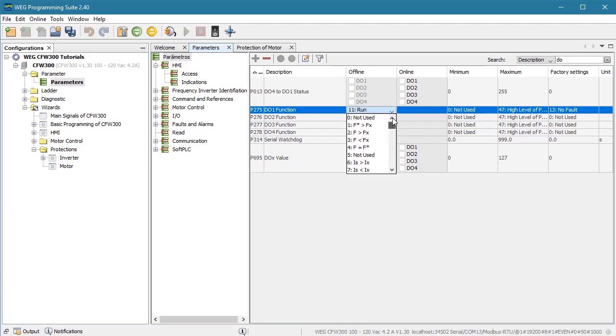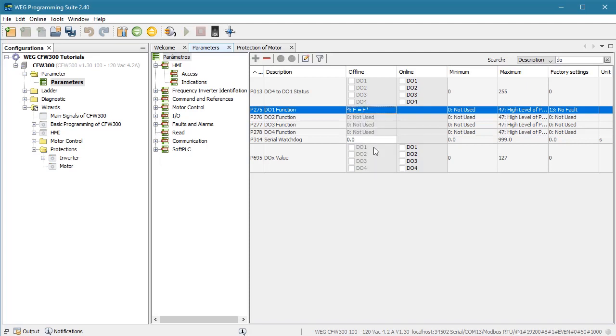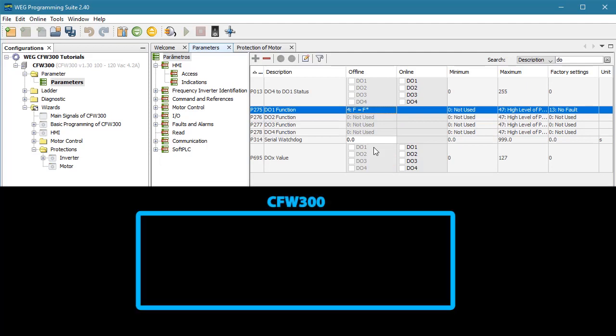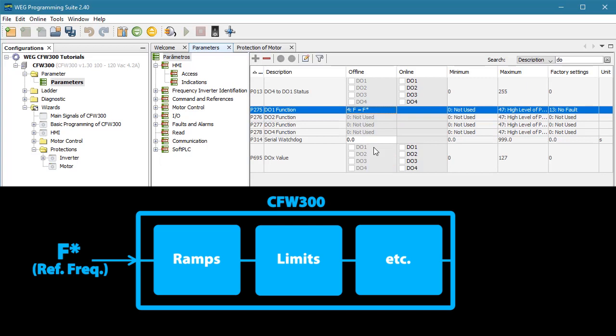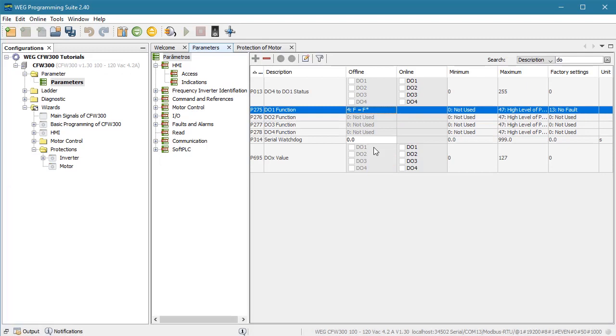There are a couple of frequency monitoring options. Let's have the light turn on when the output frequency reaches the requested reference frequency. F* is the requested reference frequency before ramps, limiting, etc. are applied. F is the final output frequency. We want to know when the output frequency F reaches the requested reference frequency F*, so we want number 4.